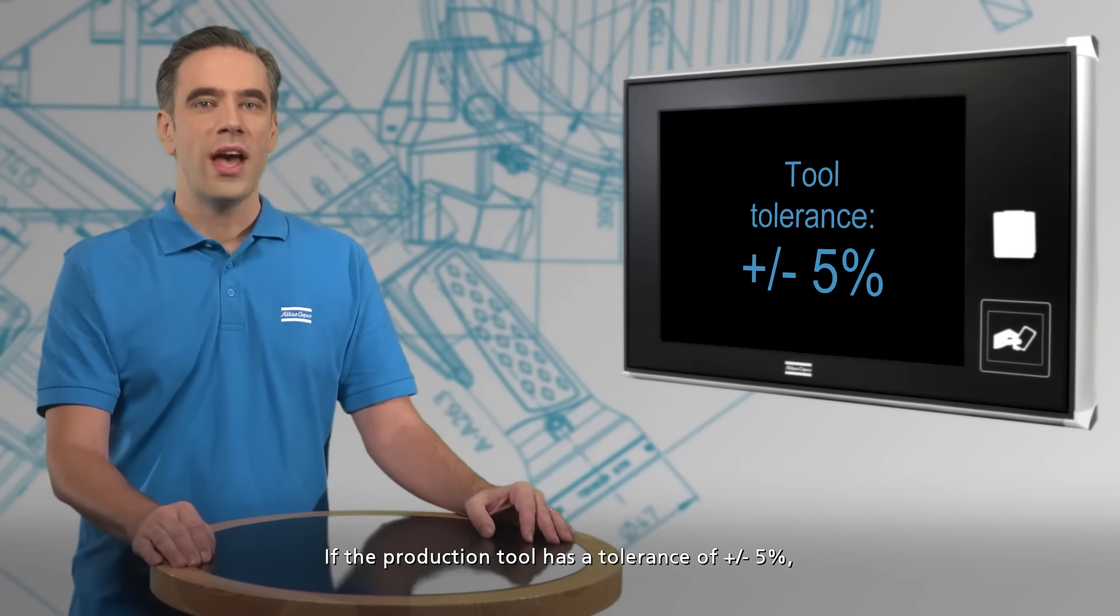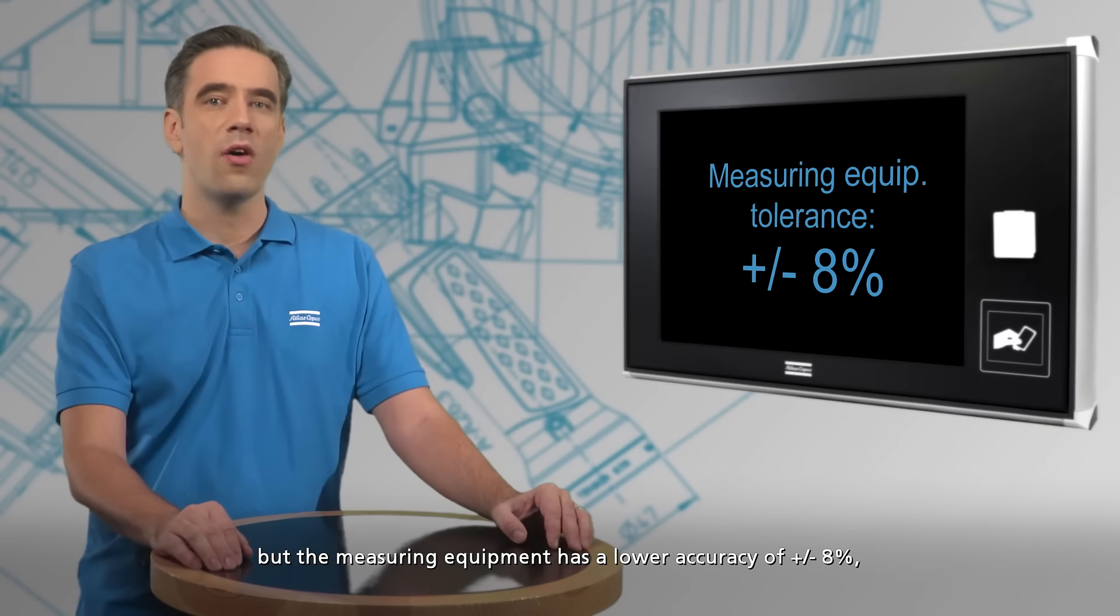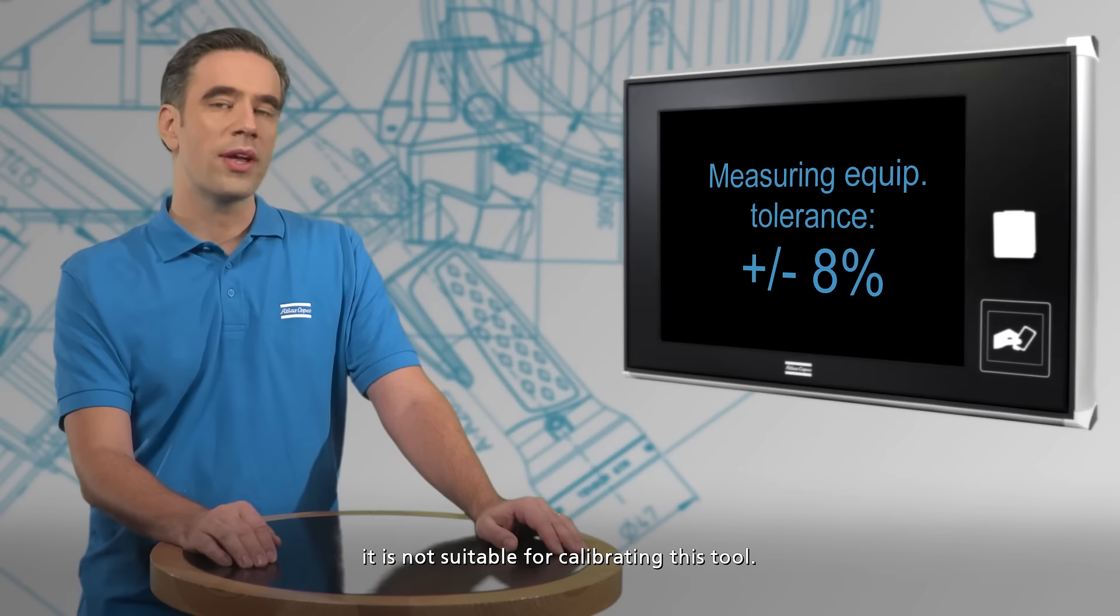If the production tool has a tolerance of +/- 5%, but the measuring equipment has a lower accuracy of +/- 8%, it is not suitable for calibrating this tool.